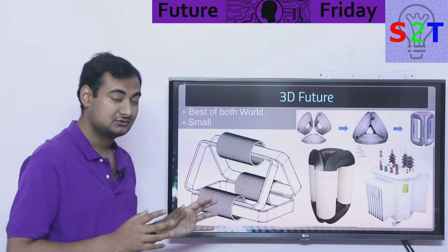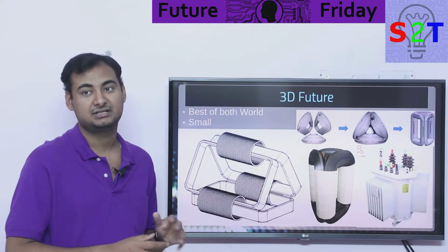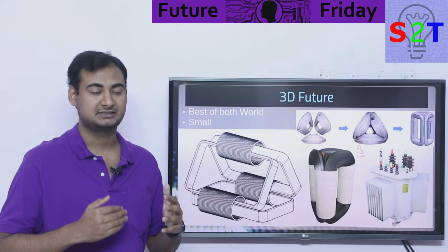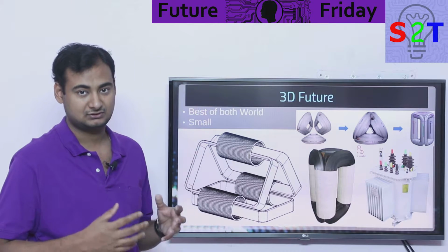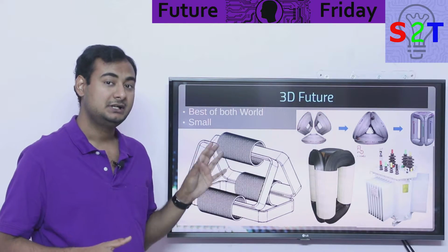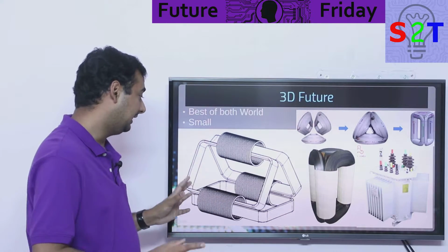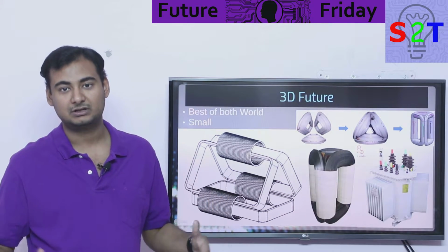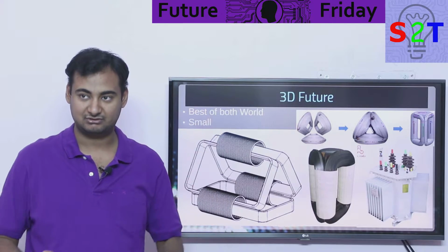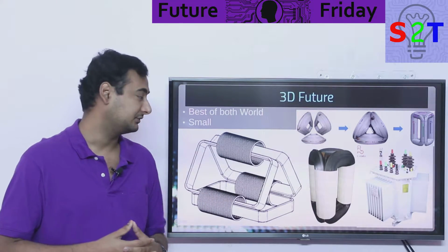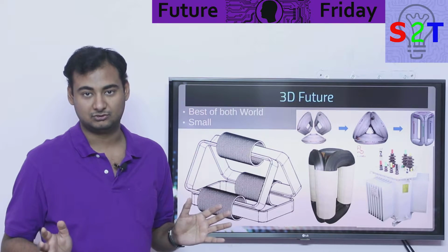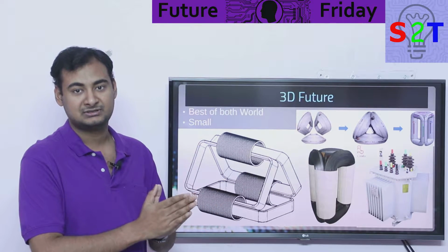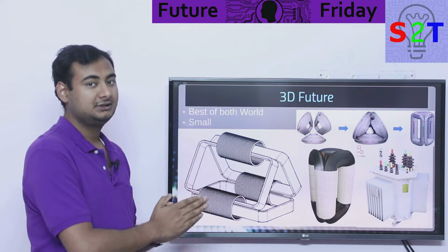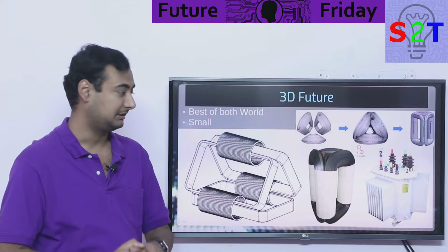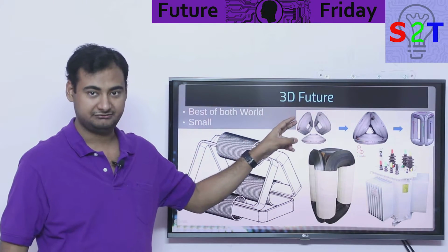In case of a three-phase transformer, this also has the advantage that if one phase goes out of sync - let's say one phase is suffering too much loss or too much power draw - it can manage and balance it out, and it does not require ludicrously more components like shell type does, because you have to lock it inside. So this is best of both worlds: you get the material consumption of core type, and the power efficiency of shell type. That is why we want to go to the 3D future.